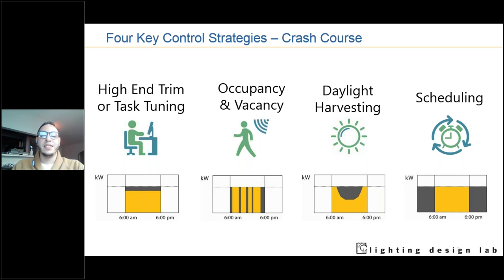With occupancy and vacancy sensing: in occupancy mode, when one sensor in a group detects a person, the lights in that space turn on. However, they will not turn off until all sensors in that area or group detect no one for a specified amount of time. The difference with vacancy is that lights will not turn on automatically. You need to turn them on via a wall station button press or a timer, but they'll still turn off after no one is detected in the space.